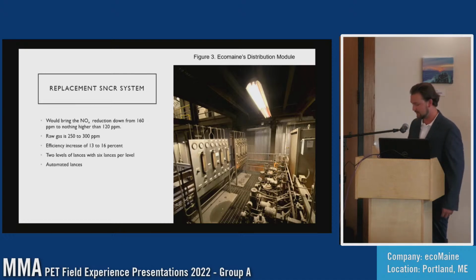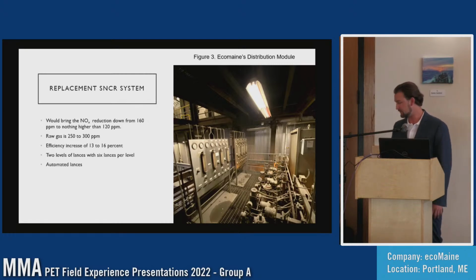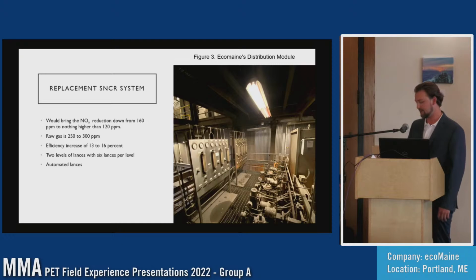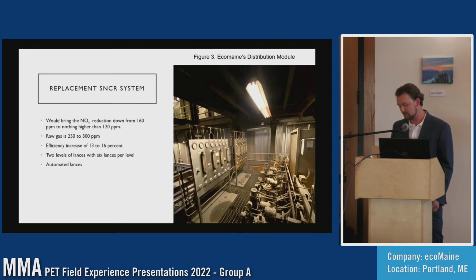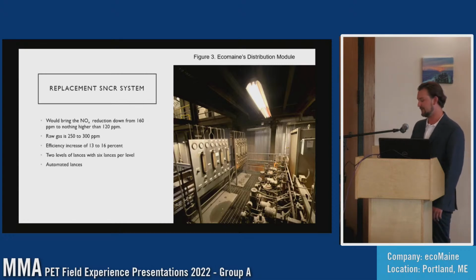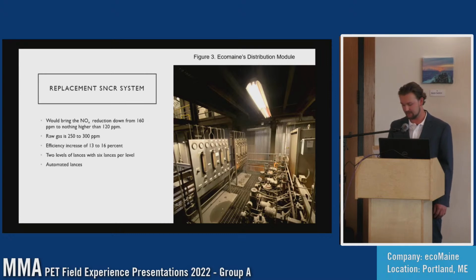Replacing the SNCR system with a newer one would bring the NOx reduction down from 160 parts per million to nothing higher than 120 ppm. The raw gas was measured by M&S Umweltechnik from March 13th through the 17th, 2022. They found the range of NOx to be 250 to 300 ppm. Doing the math, that would be a 13 to 16% efficiency increase with putting a newer system in.